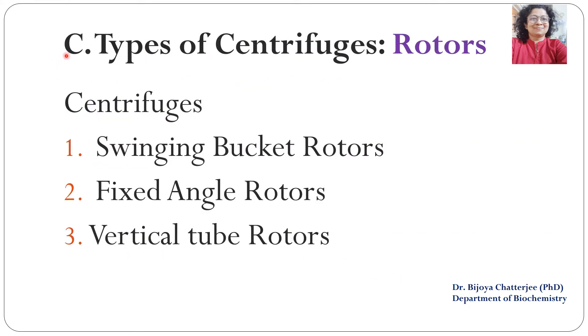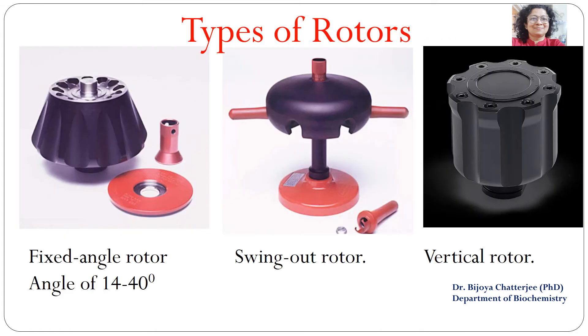The third classification is based on rotors: swinging bucket rotor, fixed angle rotor, or vertical tube rotors. The fixed angle rotor has an angle of 14 to 40 degrees of the bucket from the axis of rotation. The swing-out rotor has buckets that swing out while the axis is rotating. The vertical rotor has the bucket angle exactly parallel to the axis of rotation.